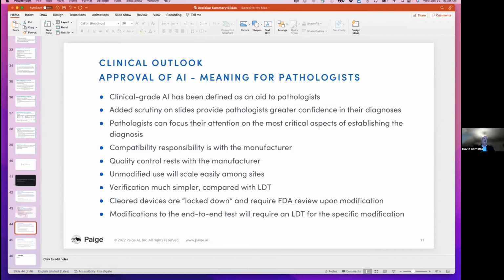The compatibility is the responsibility of the manufacturer, as is the quality control. And that's obviously very important if you compare something, for instance, to a laboratory developed test, where all of that rests with the individual laboratory. This also allows the laboratory to scale use. If you have a multi-site laboratory, you can undertake a single verification and then use the product in all your sites, as opposed to laboratory developed tests, which require independent CLIA validation for each physical location. And the verification that Jansen described is actually quite a lot simpler than preparing your own laboratory developed test.